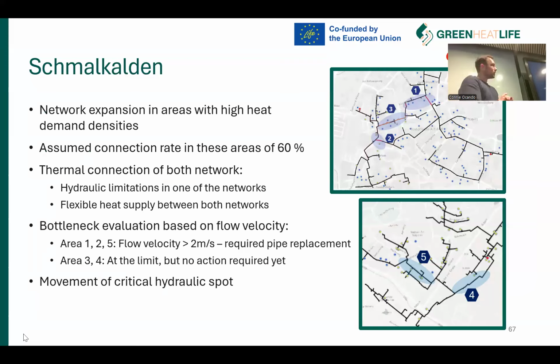The analysis of the digital twin showed us that the connection is possible. We expanded the network along the highest heat demand densities around the city, assuming a connection rate of 60%. The digital twin showed us it's fine, you can expand the network. The current pipes can handle the increased volume flows and supply, except for some critical areas I've highlighted here.